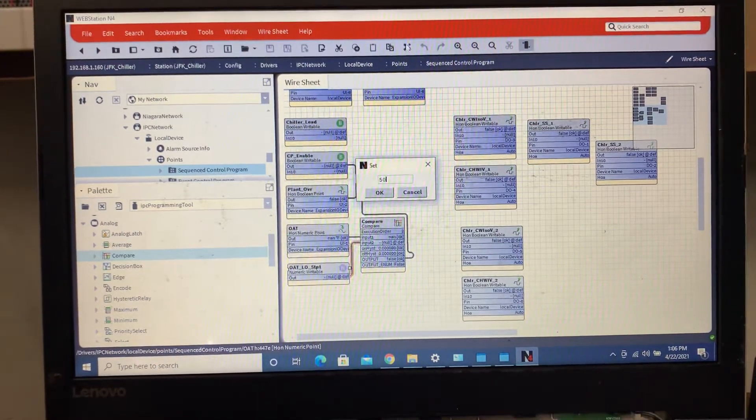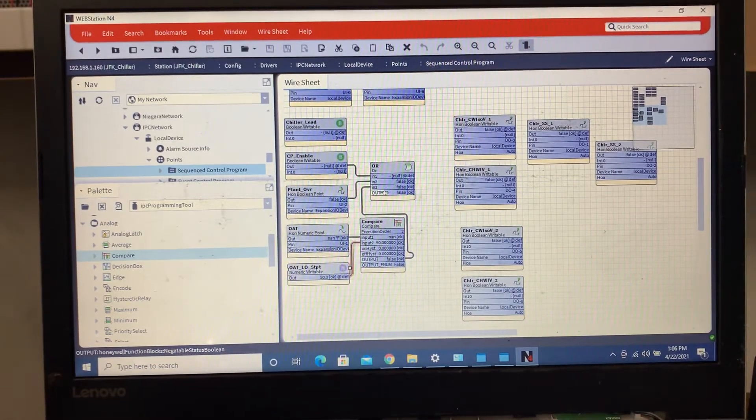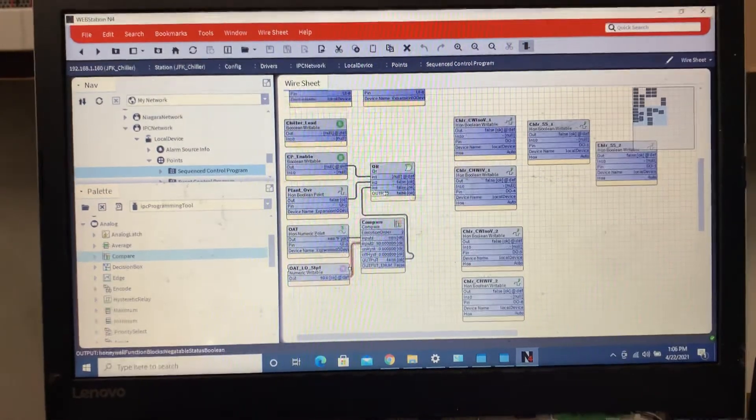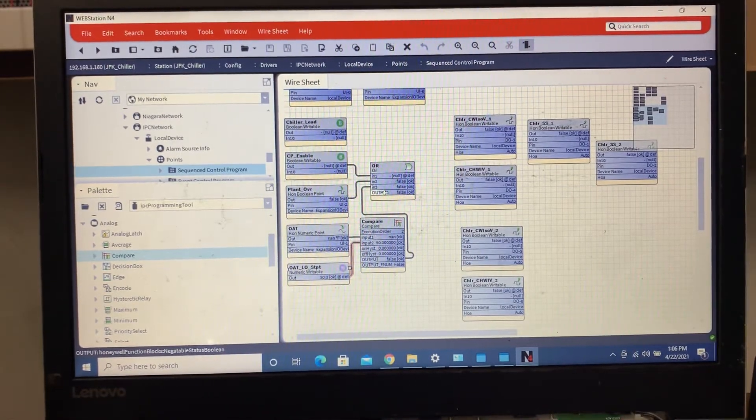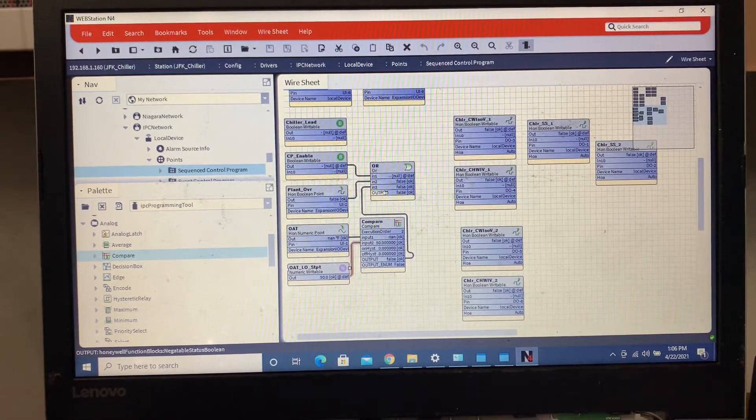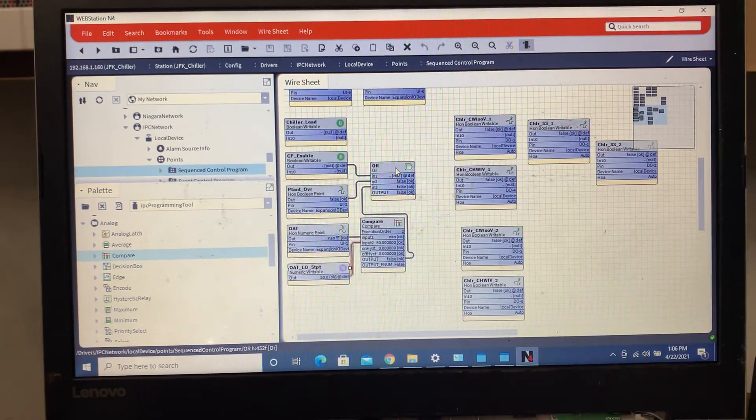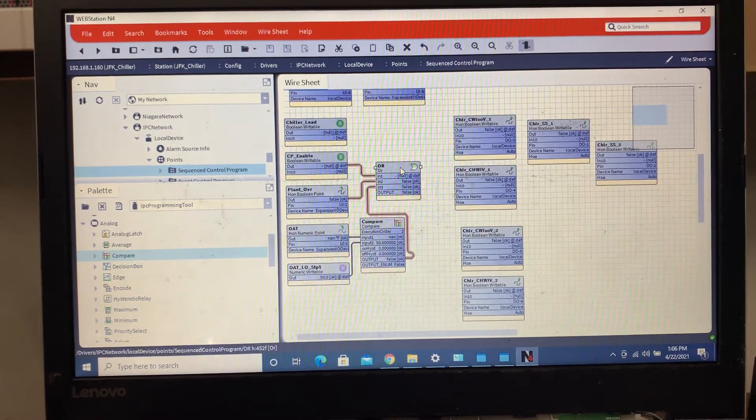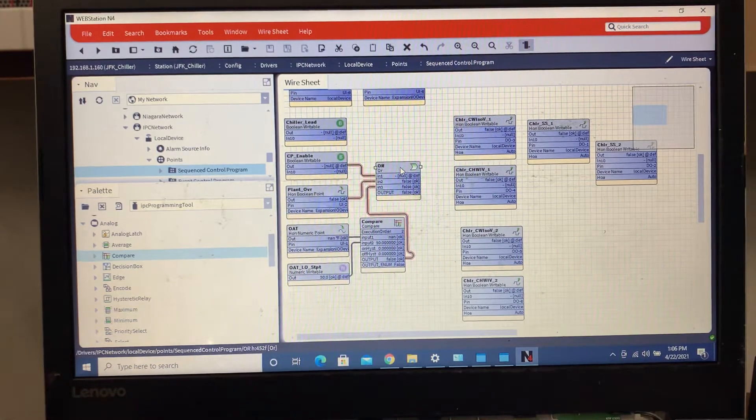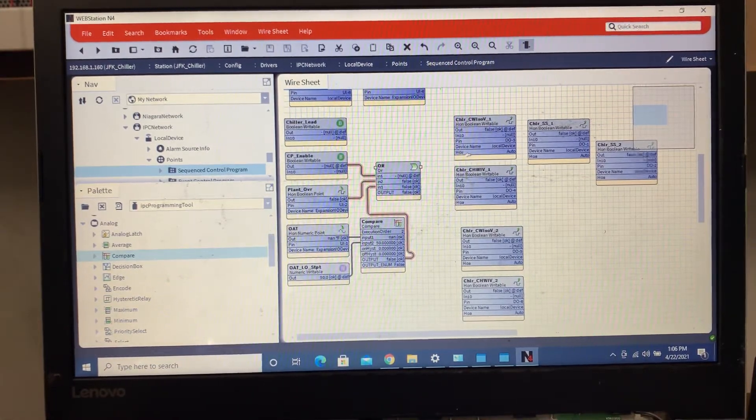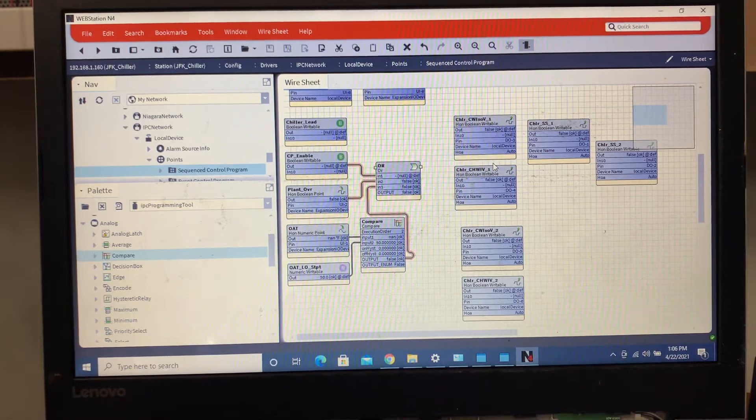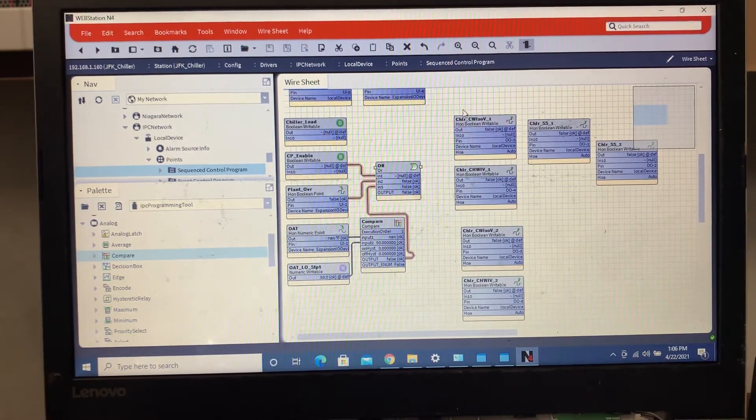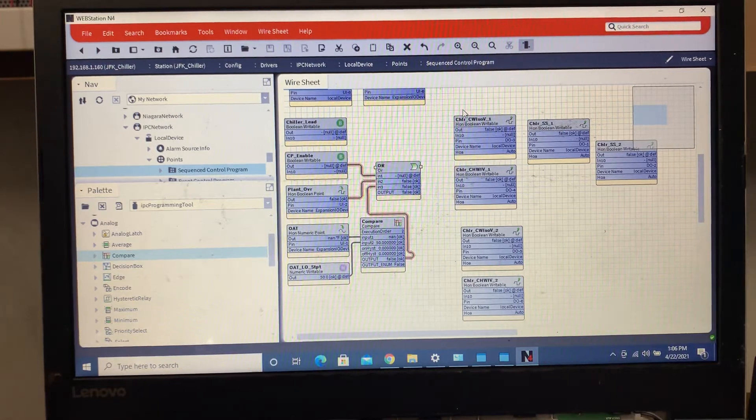Actions set, they want anything below 50 degrees outside air temperature to lock out their chillers. Even though it's a low pressure system, they have some older chillers here, so they prefer to get a little bit of a load on them before they decide to bring them on on the cold days and the shoulder days, which we have a good bit of them here in Houston because we'll go from 60 degrees to 90 in three, four hours.